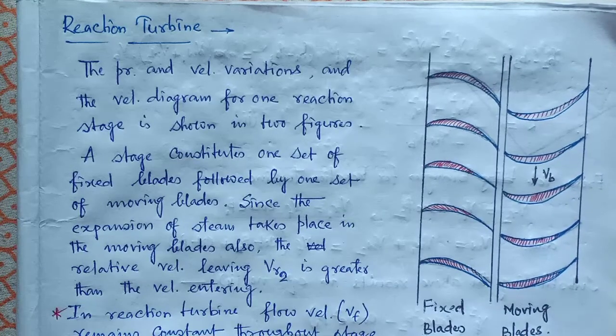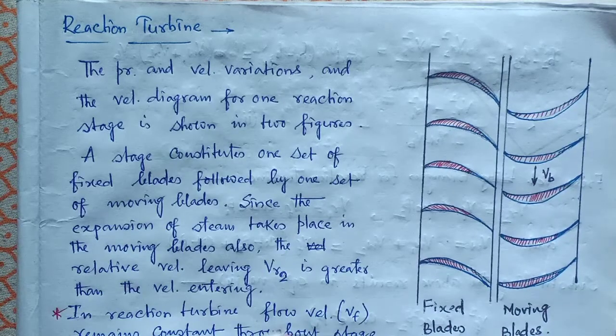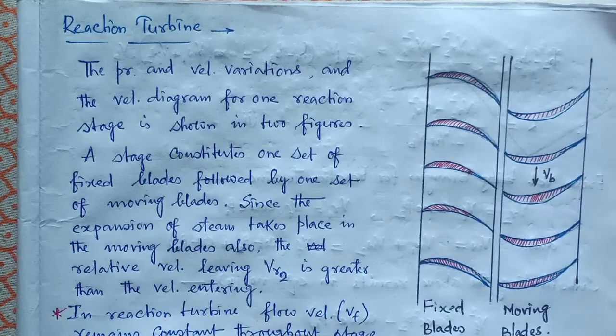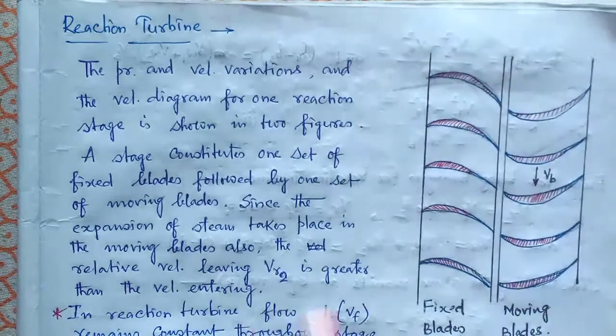As mentioned earlier, the fixed blades are asymmetrical, having a decreasing area towards the exit side, resulting in expansion and increase of speed. Obviously it was mentioned already. In a reaction turbine the same thing is done with the moving blades, giving them exactly the same shape as the stationary ones.